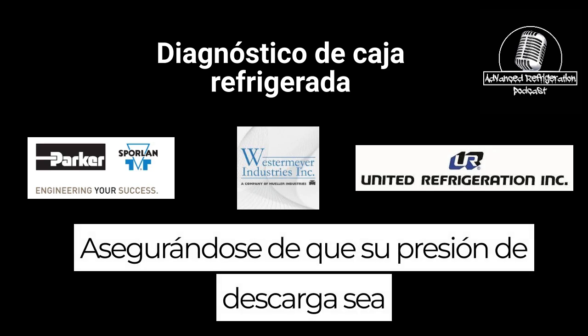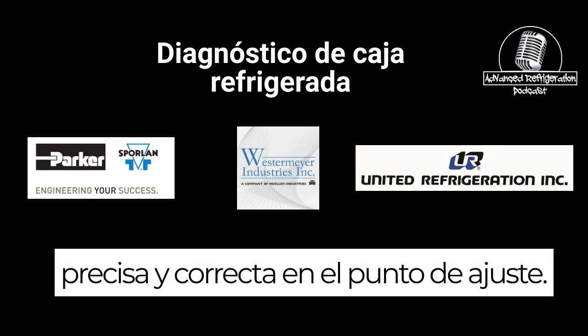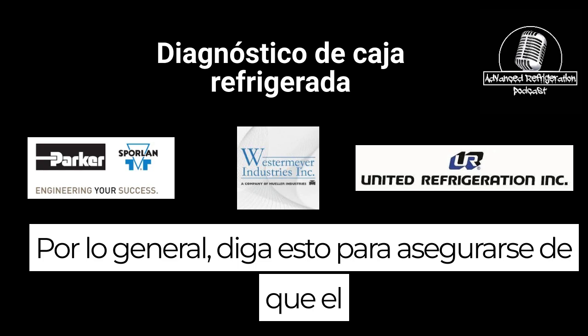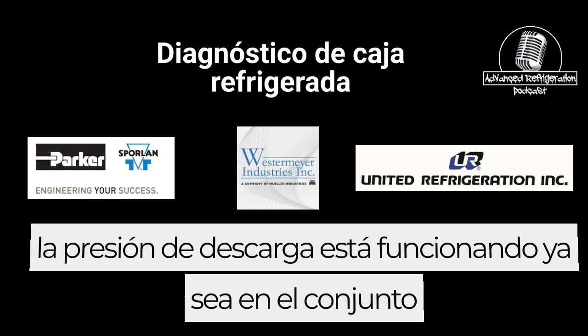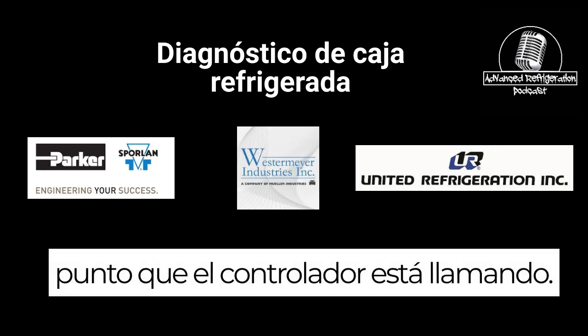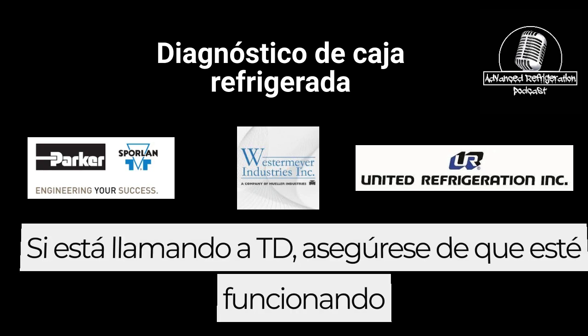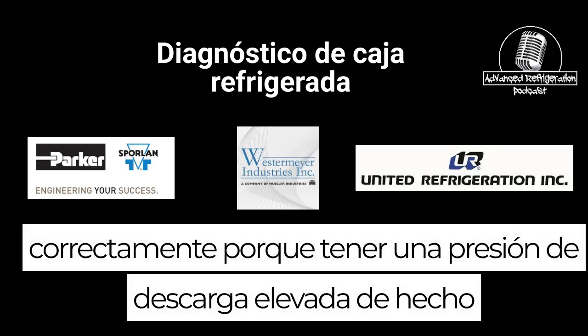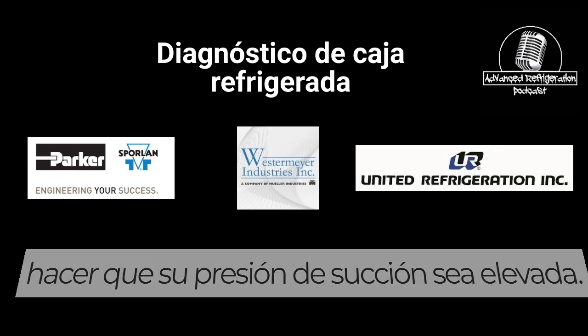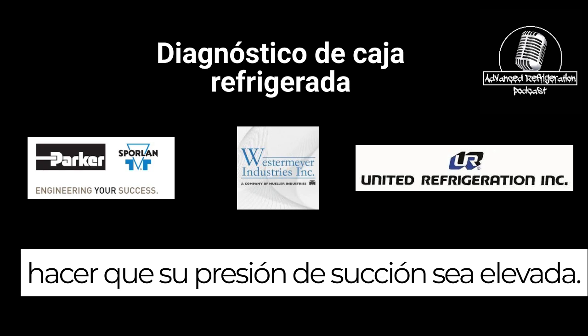Making sure that your discharge pressure is accurate and right at set point. We usually tell this to make sure that the discharge pressure is running at the set point that the controller is calling for. If it's calling for TD, make sure it's working properly, because having elevated discharge pressure will in fact cause your suction pressure to be elevated.